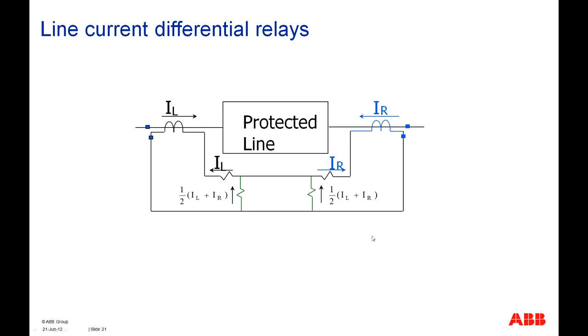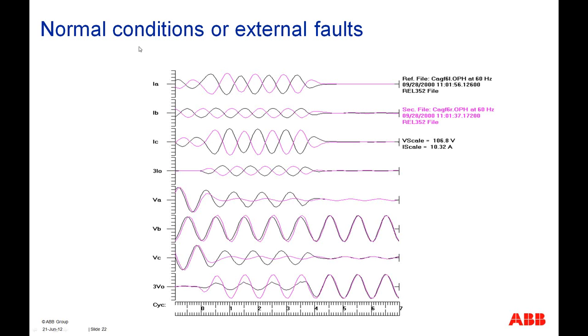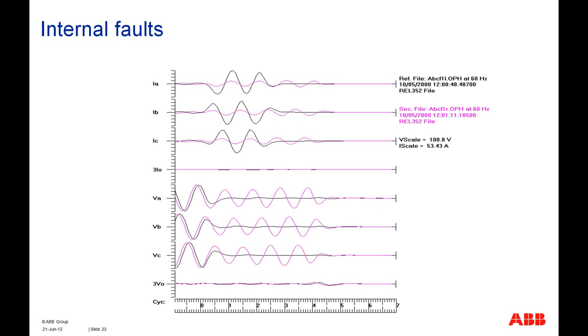So in that case, half of the operating current will flow in the, let's say, local box, and half of the operating current will flow on the remote box. Here you can see that in normal conditions or external fault conditions, these two currents are exactly opposite to each other. So they are forming the operating current equal to 0 and therefore no trip. And in this case, these two currents are in phase and therefore depicting that this fault current is for the internal fault and therefore will get a tripping.